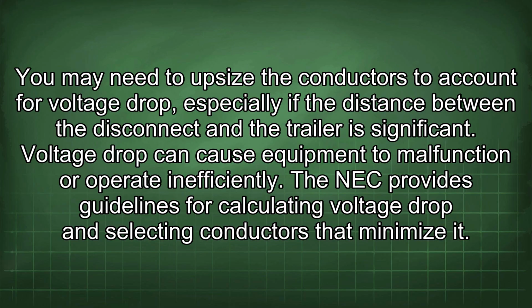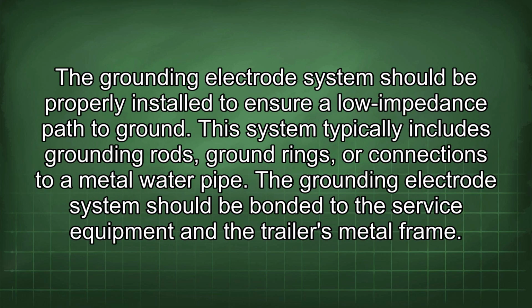You may need to upsize the conductors to account for voltage drop, especially if the distance between the disconnect and the trailer is significant. Voltage drop can cause equipment to malfunction or operate inefficiently. The NEC provides guidelines for calculating voltage drop and selecting conductors that minimize it. The grounding electrode system should be properly installed to ensure a low impedance path to ground. This system typically includes grounding rods, ground rings, or connections to metal water pipe. The grounding electrode system should be bonded to the service equipment and the trailer's metal frame.